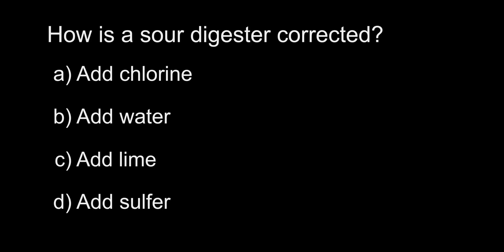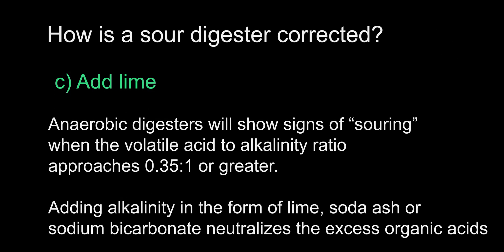How is a sour digester corrected? A. Add chlorine, B. Add water, C. Add lime, D. Add sulfur. The answer is C, add lime. One of the most important factors when operating a digester is watching the volatile acid to alkalinity ratio — monitoring the buffering capacity, which represents the ability of a digester to neutralize the acids formed during digestion. You will see a change in the volatile acid to alkalinity ratio before you see a change in pH. Adding lime increases the alkalinity and buffering capacity, helping keep your pH stable. I encourage you to learn more about digesters, as there will certainly be other questions regarding them on your exam.